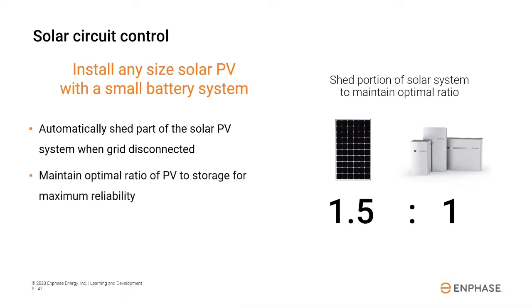So this is a great option where you have customers that want a large PV system because they've got a big electric bill to offset, but they don't necessarily want a huge battery system to go with it. They might just want one Encharge 10 just for their essential loads. So this gives you that option. And then once the system is reconnected to the utility grid, that portion of the PV that was turned off is automatically going to be restored.